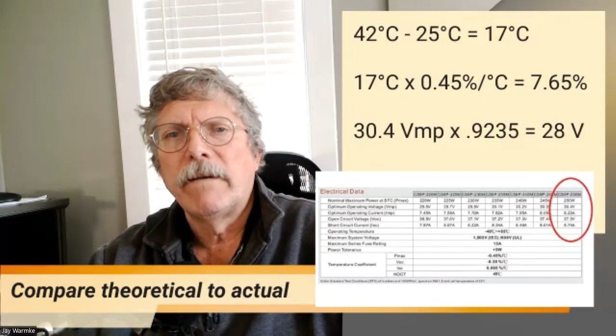So we look at the Vmp, which is how many volts this panel is going to produce when operating at standard test conditions, times 92.35%, or 0.9235. And we find now that that panel is only going to produce about 28 volts. All right, so instead of the 30.4 volts, it's going to produce 28 volts. We did that by adjusting voltage for temperature.